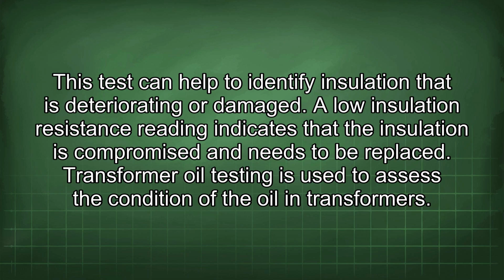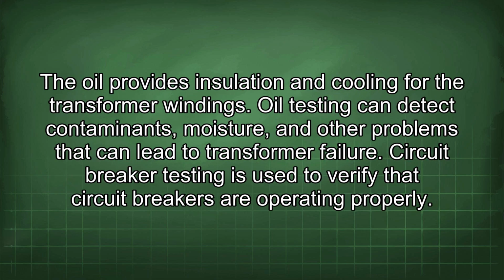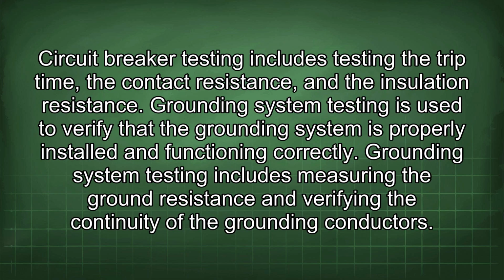Transformer oil testing is used to assess the condition of the oil in transformers. The oil provides insulation and cooling for the transformer windings. Oil testing can detect contaminants, moisture, and other problems that can lead to transformer failure. Circuit breaker testing is used to verify that circuit breakers are operating properly. Circuit breaker testing includes testing the trip time, the contact resistance, and the insulation resistance. Grounding system testing is used to verify that the grounding system is properly installed and functioning correctly.